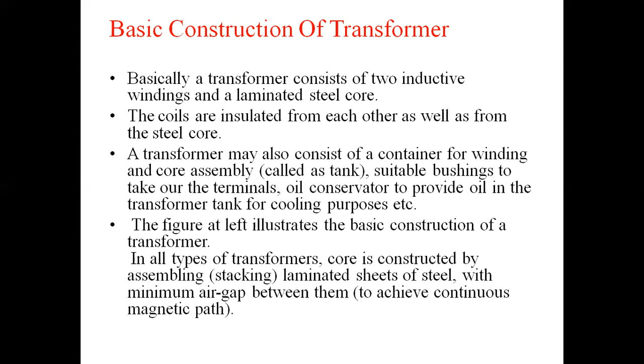Here, in all the types of transformers, the core is constructed by assembling, stacking laminated sheets of steel with the minimum air gap between them. Why? Because to achieve the continuous magnetic path. The steel used has high silicon content and is sometimes heat treated to provide high permeability and low hysteresis loss. Laminated sheets of steel are used to reduce the eddy current losses.